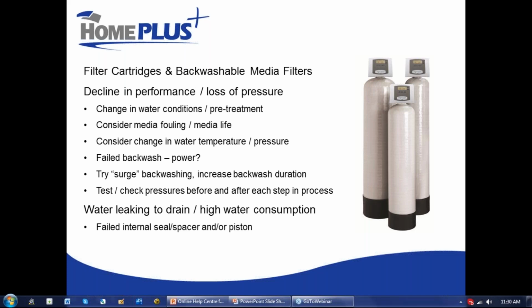And one of the other problems I wanted to mention that's quite common is related to a missed maintenance opportunity. Probably a good way of describing it is inside these control valves, essentially you have a little motor that's connected to a timer. The timer decides when a backwash is supposed to occur, and the motor moves a little piston. The piston opens up ports that are sealed by what we typically refer to as a seal and spacer stack. And all of those are wear and tear parts. They definitely do not last forever. And in most cases, you're replacing them every 2 or 3 years.